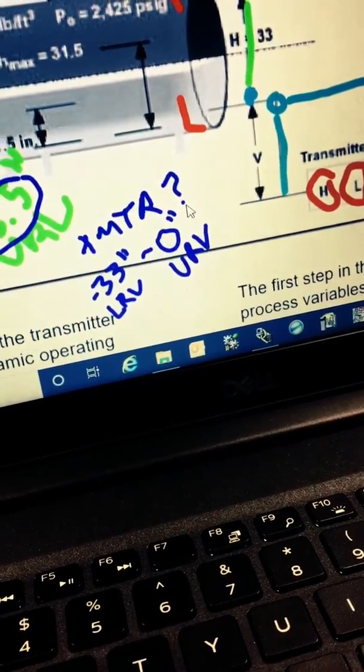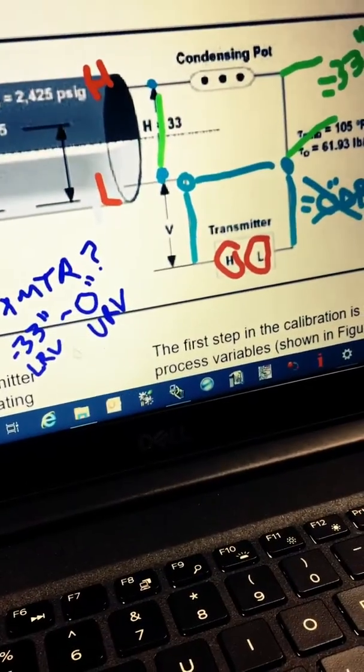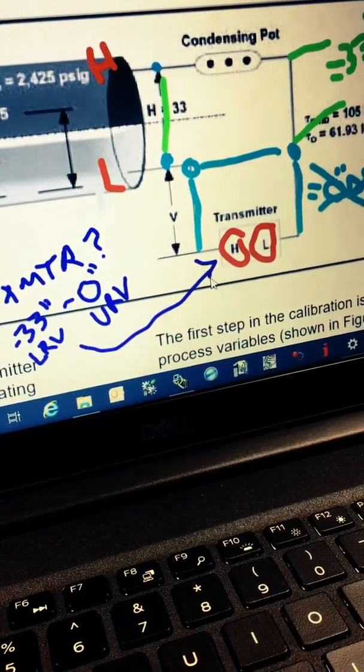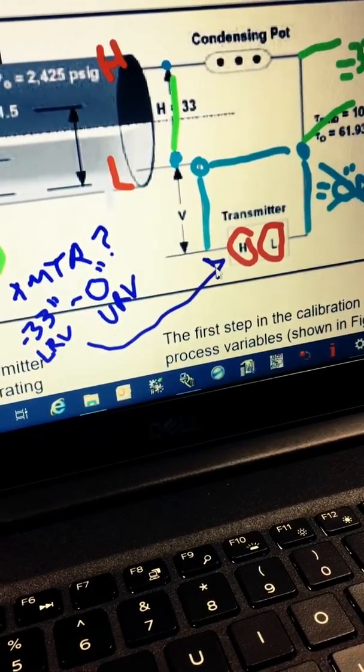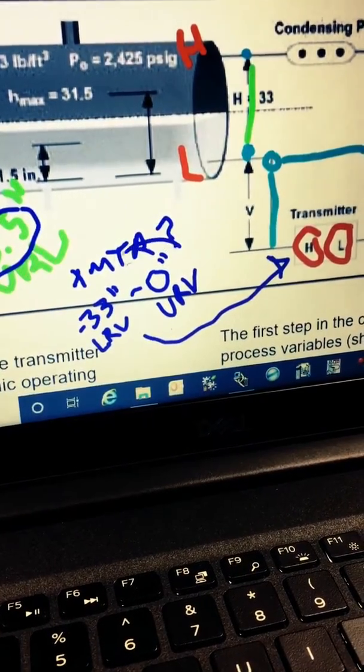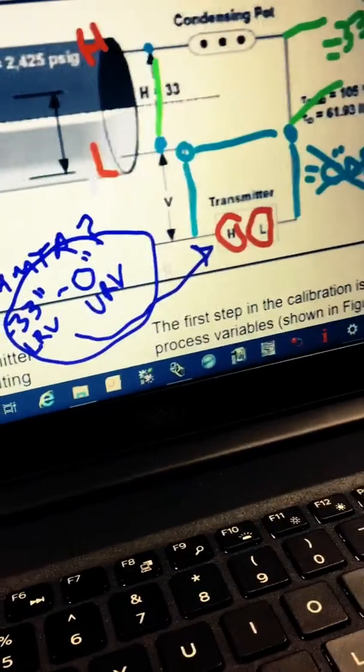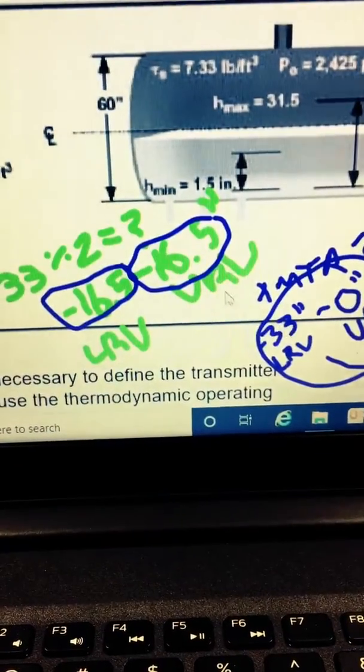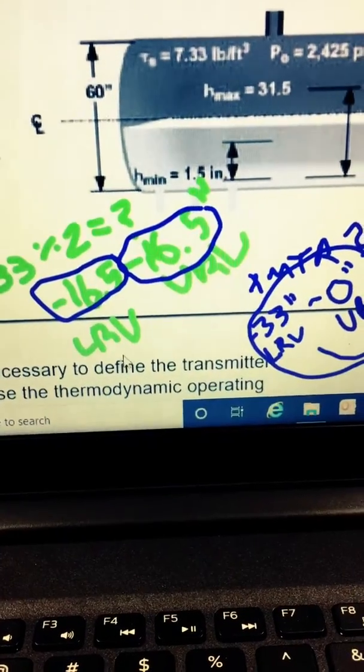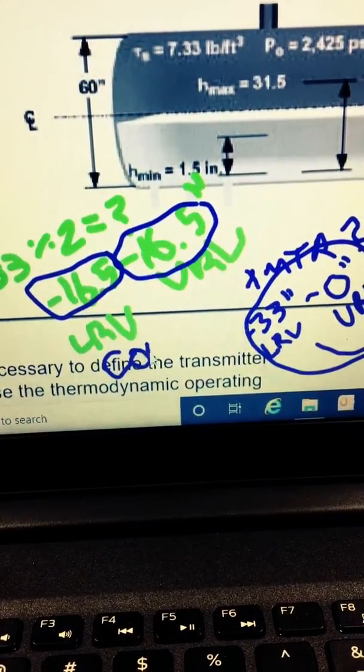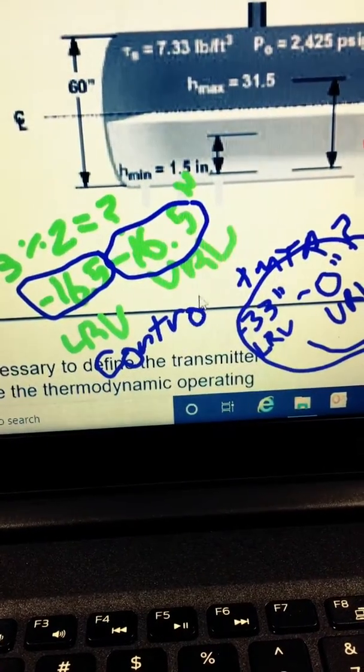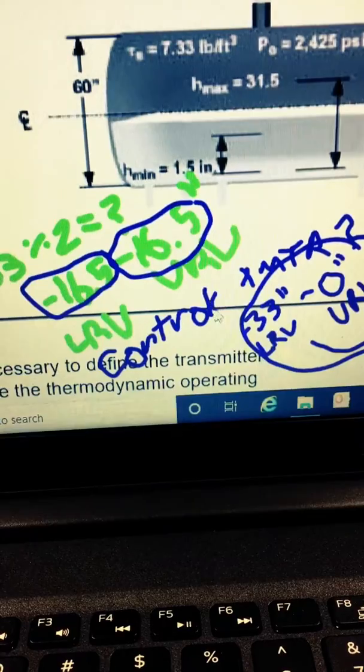Now, keep in mind, if it was tapped low to low, high to high, that would be a 33 inch lower range value and a zero inch upper range value. But because we tubed it low to high, high to low, it's going to be a negative 33 inch LRV with a zero inch URV. And we're going to have a control range of negative 16 and a half inches to plus 16 and a half inches.